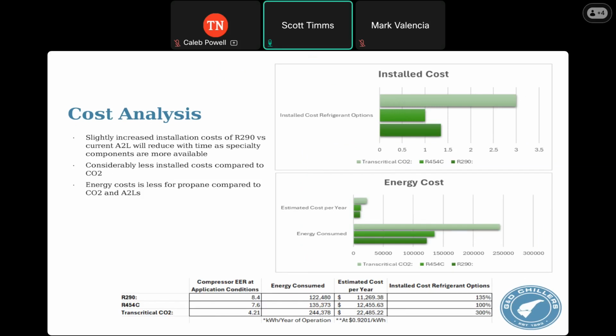That being said, it's considerably less compared to CO2. You can see in the bottom right, we kept 454C as the one-to-one basis, so that's 100%. The R290 is 135% - this was a year ago, we've gotten that number down closer to 115% now. Transcritical CO2 is about 3x, and that number isn't going down essentially because of the operational complexity required. You can also see here that the estimated energy cost is several percent lower for R290 as opposed to R454, and then once again about half of what it was expected for CO2.